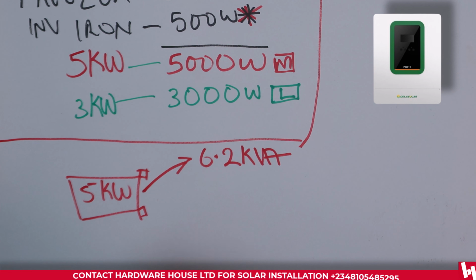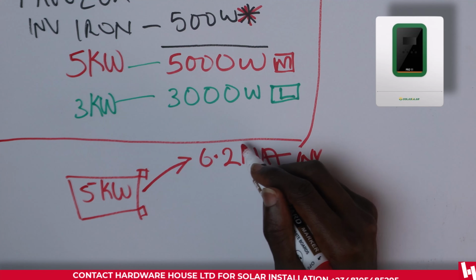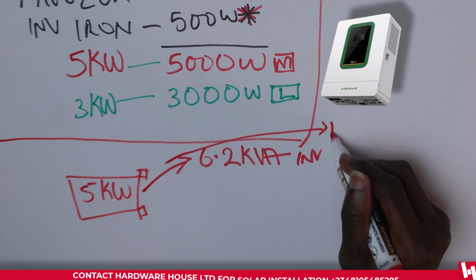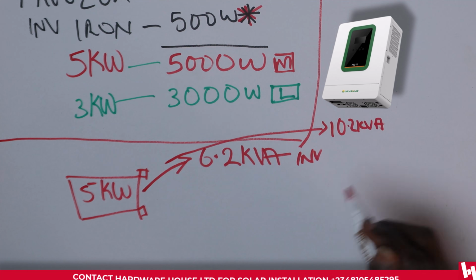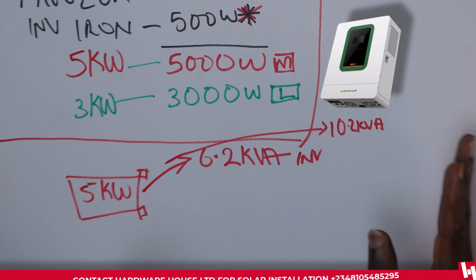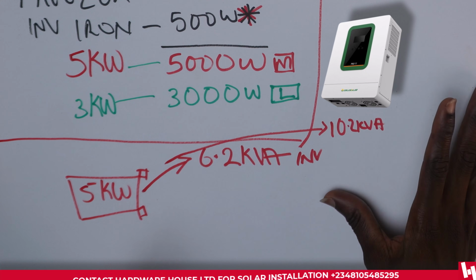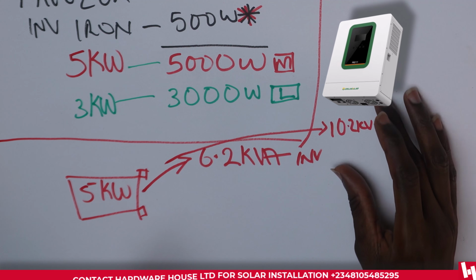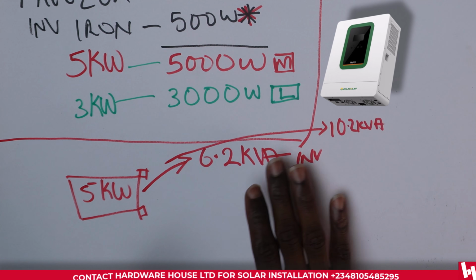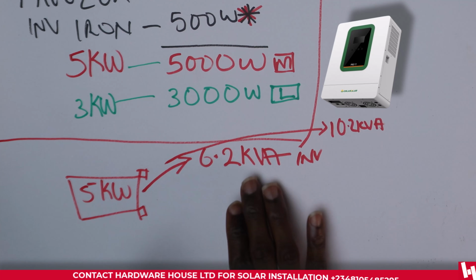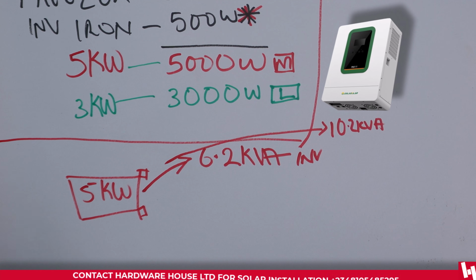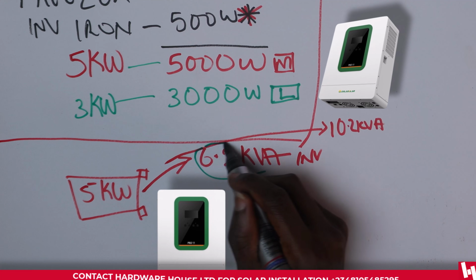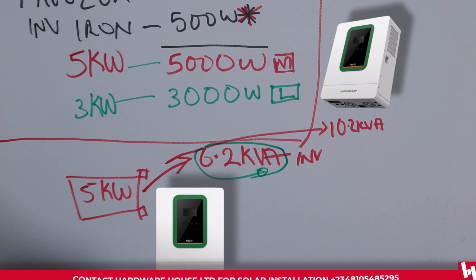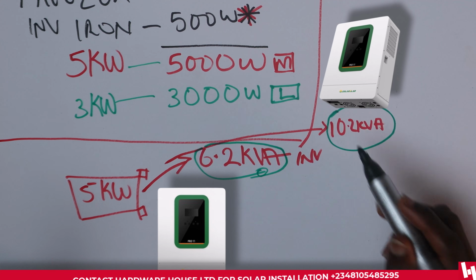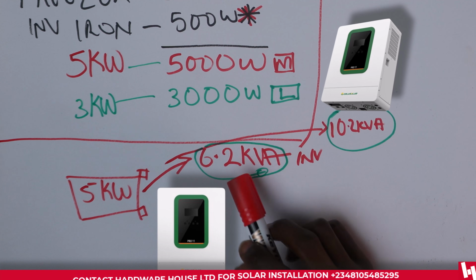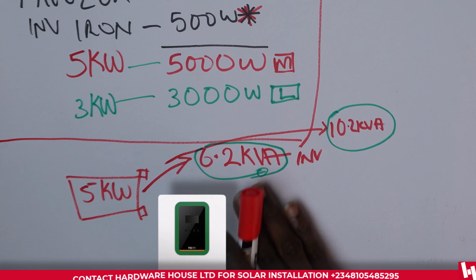kVA or kilowatt inverter. We would have actually gone further to give him a 10.2 kVA so that he can do daytime running together with the solar, so there isn't much sag on the battery. But during the night, he wouldn't max out this 10 kilowatt on the inverter. The load is going to drop to below this 6.2. But we decided to go for this because, number one, this client wanted the most cost-effective as opposed to an overkill design. So we went for a 6.2 kVA and it's performing wonders.